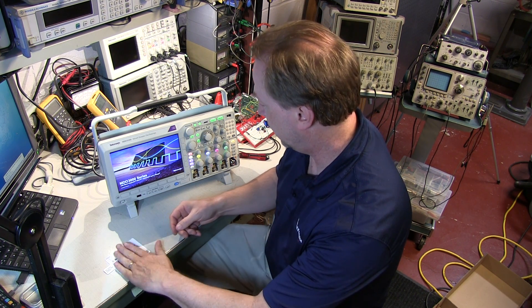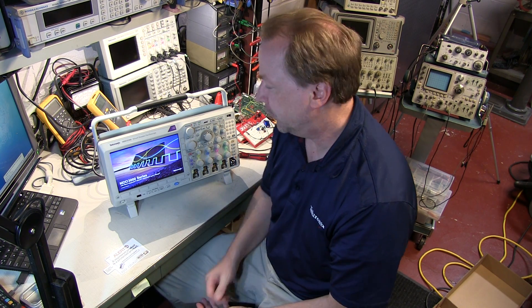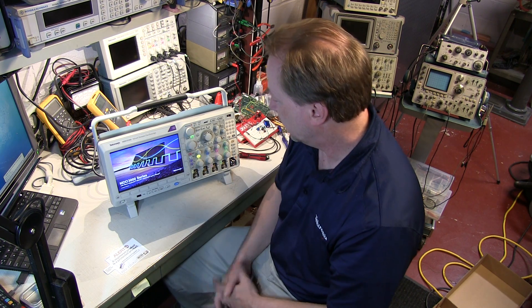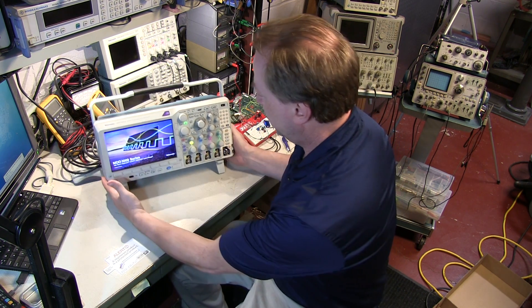So we can see it firing up here. Most of these scopes, they're loading firmware and things like that as they're booting up. So it's not unusual for them to take 30 seconds to a minute to boot.